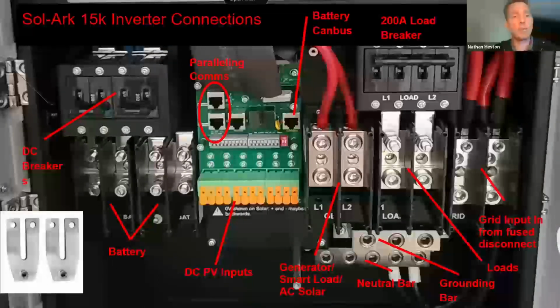Again, continuous input from the DC side on the Sol-Ark 15k is 275 amps continuous. The breakers are oversized there so that you can surge, not for continuous.